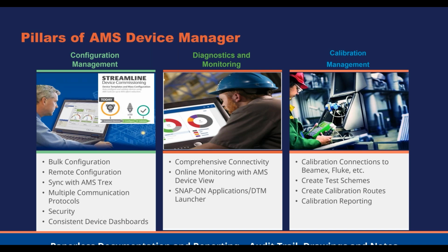Then the third pillar, calibration management. So we do calibration management, we don't do calibration. There's no software in the world that can do calibration. In order to calibrate an instrument, you need a more accurate instrument next to it so you can compare, and that's what documenting calibrators do. AMS Device Manager connects to, I would say, all of the documenting calibrators, just because I have not seen one in the market that we cannot connect to. But for the sake of exercise, Beamex, Fluke is probably more common in the market, and we connect to those ones as well, of course.